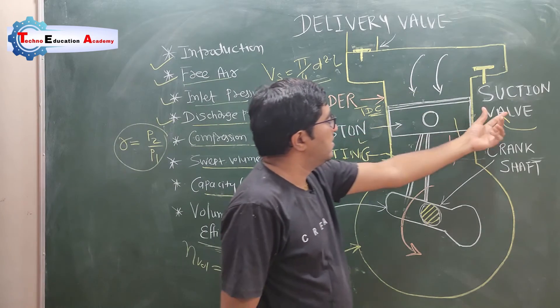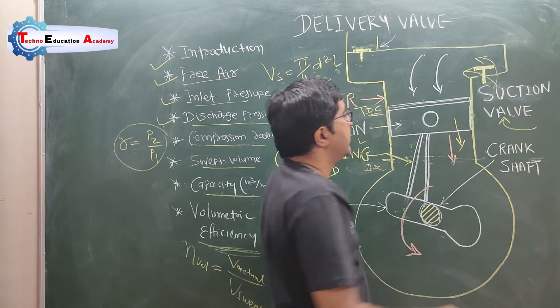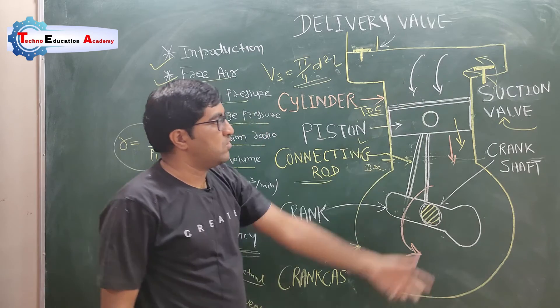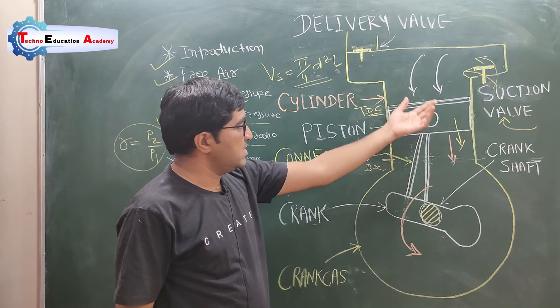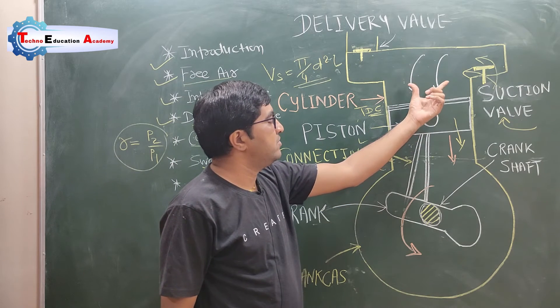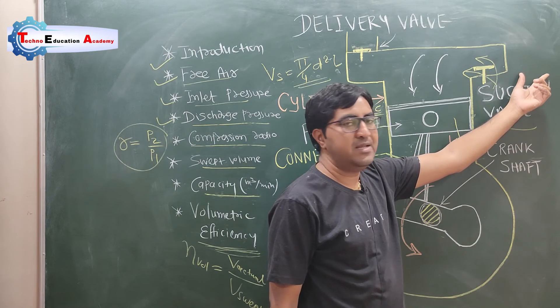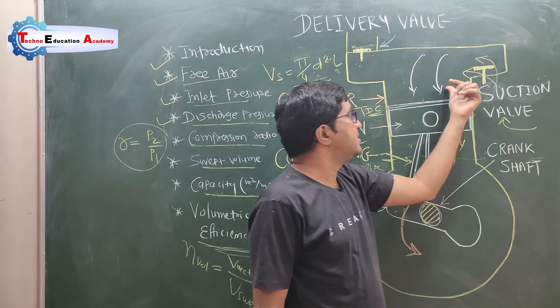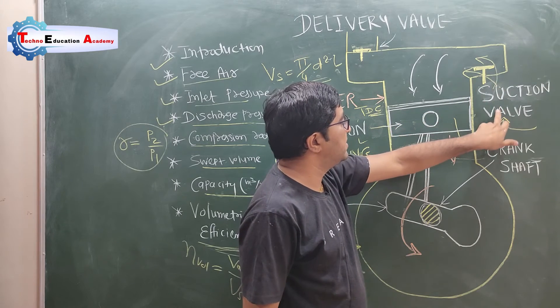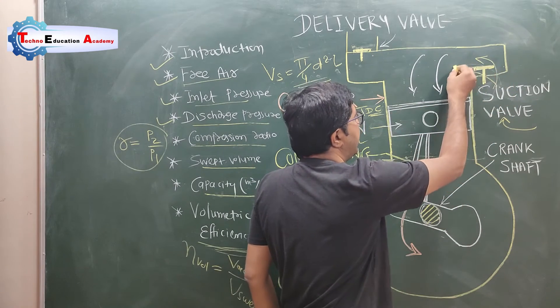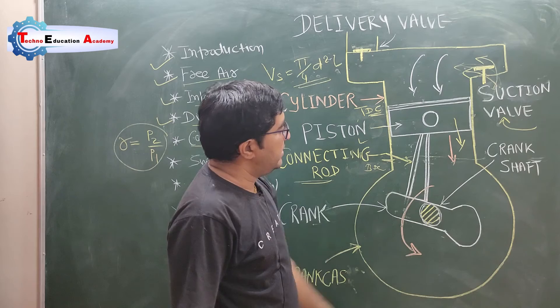Due to this negative pressure, the suction valve (inlet valve) opens and allows air into the cylinder. Since energy always flows from high grade to low grade, the atmospheric air outside the compressor — which is at a higher (positive) pressure than inside the cylinder — is sucked in through the suction valve. You can see the flow of air entering the cylinder. This is called the suction stroke.